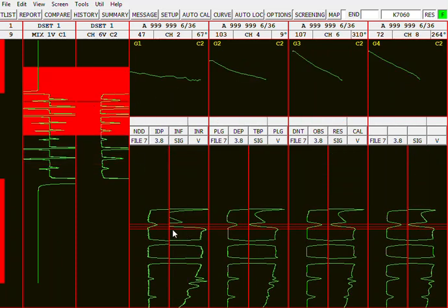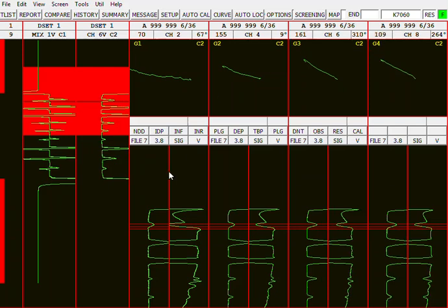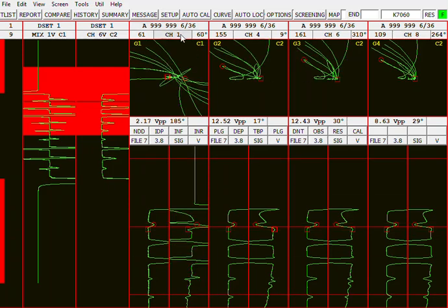And if I go to a shallow ID flaw, which is right here, it's big. That's why the signal looks like that. But it starts off at 9 degrees, 17, 30 degrees. And on channel 8, there's not a lot of phase spread, so we're not going to depend on that phase angle too much. But if you look at these flaw detection frequencies for the absolute, the ID flaw is rotating clockwise with decreasing test frequency.